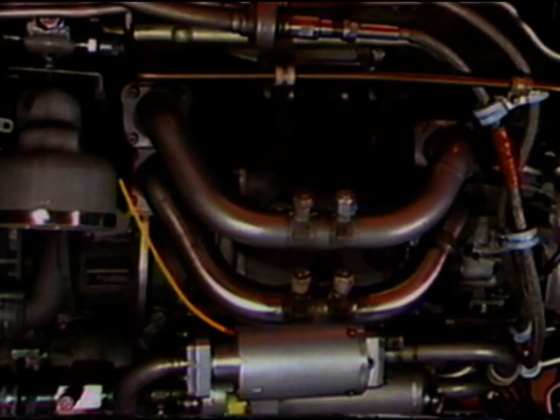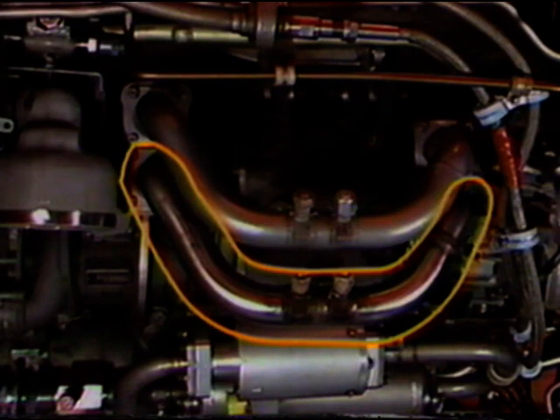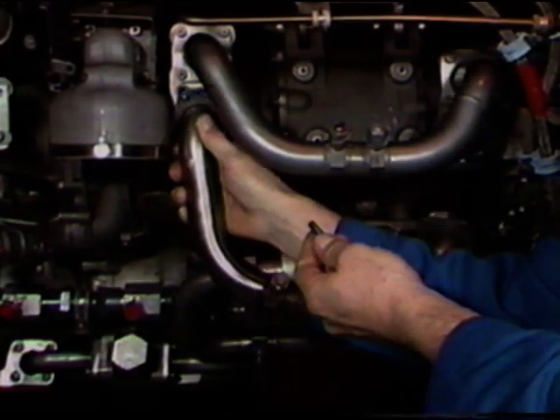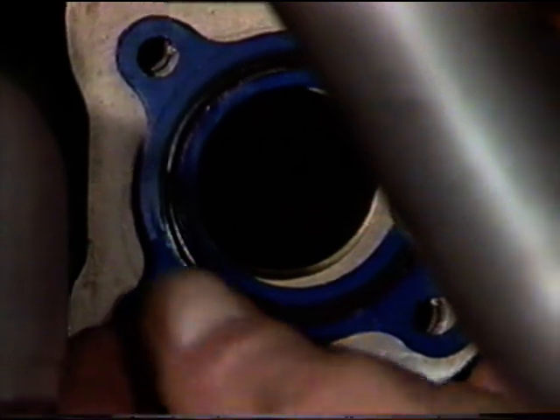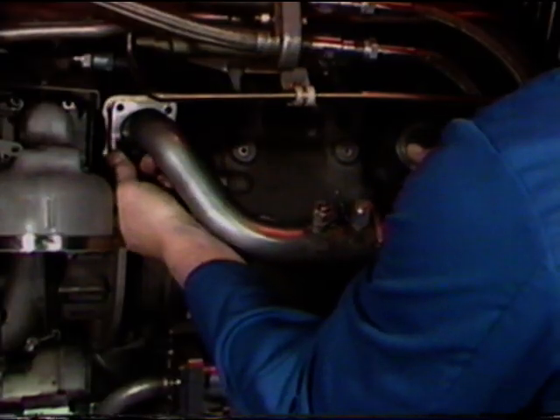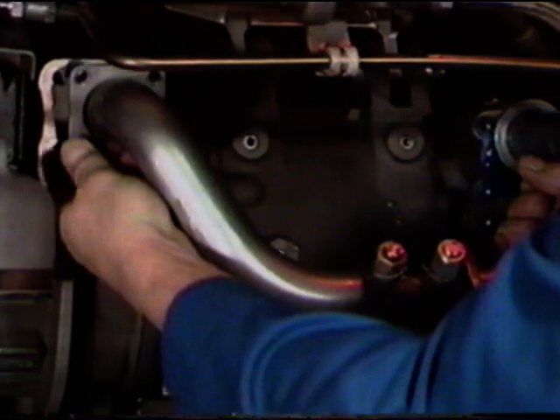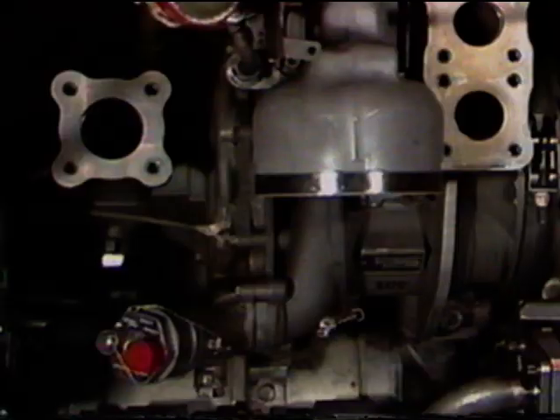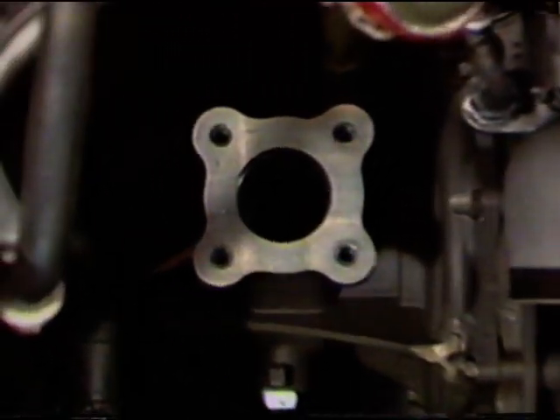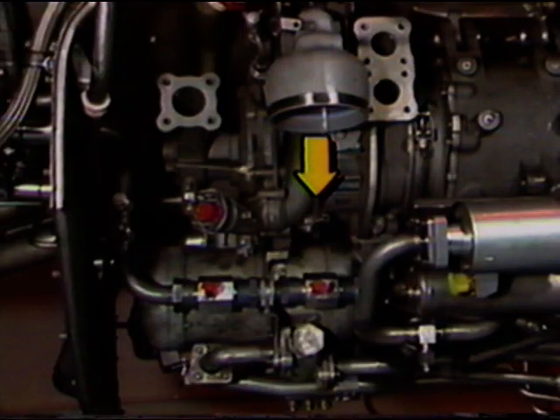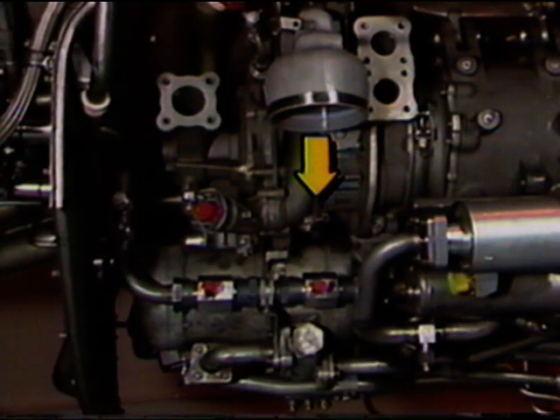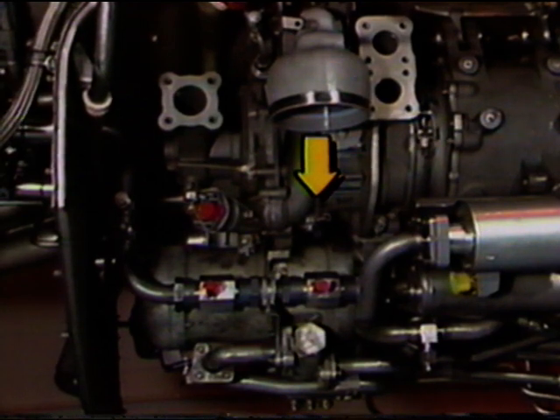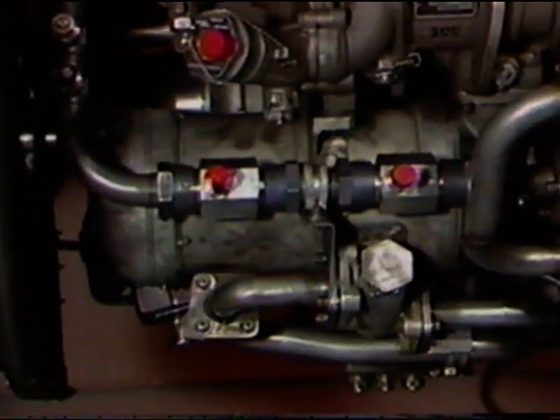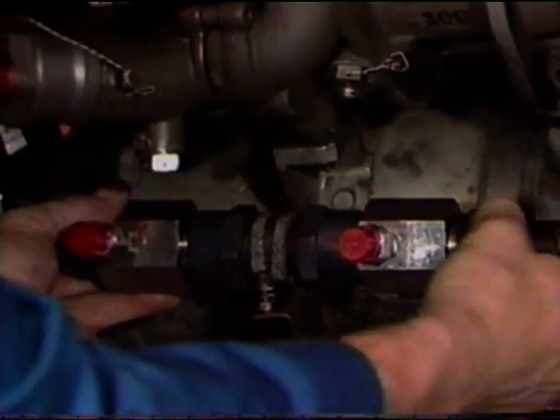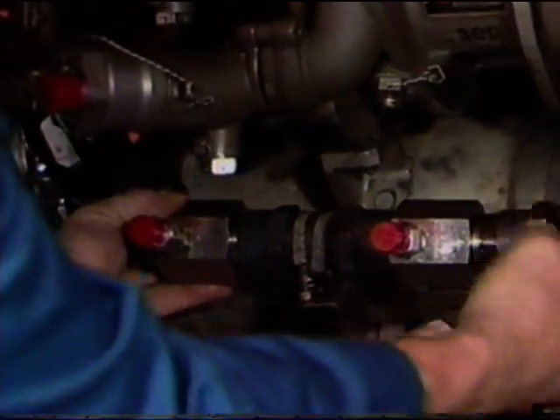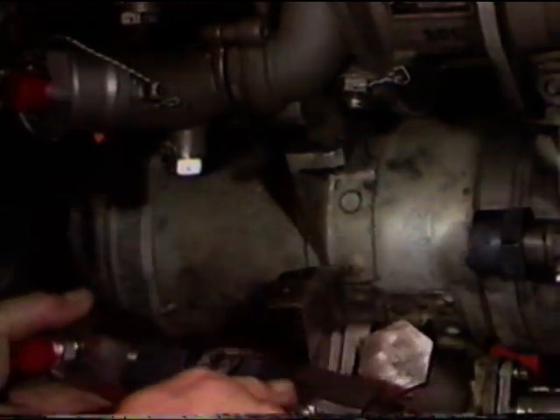Next, disconnect the control bypass return fuel tube from the bypass port by removing the bolts and washers. Then remove the gasket. Do the same in removing the pump to control fuel tube from the discharge port. Also, disconnect the fuel inlet tube. Now, remove the drain line tube from the base of the fuel pump located below the MEC discharge port. Remove and retain the union. The main fuel discharge line to the fuel manifold is removed for viewing purposes of this program.